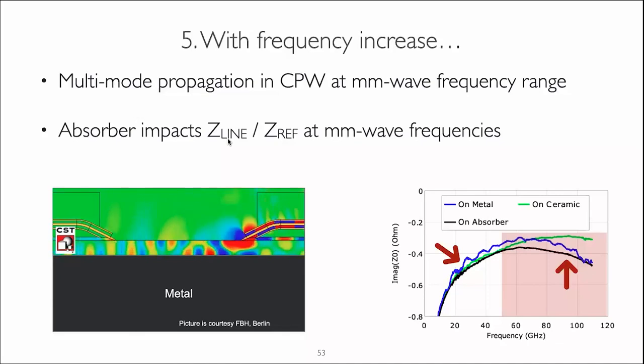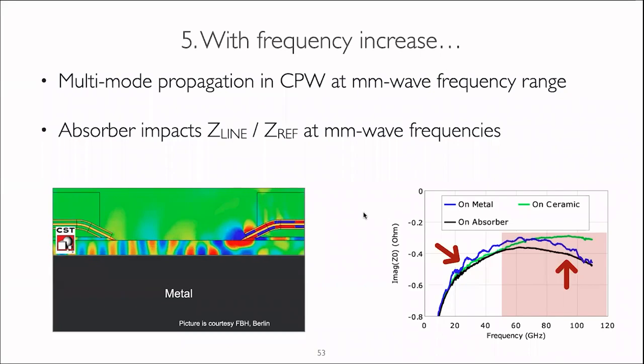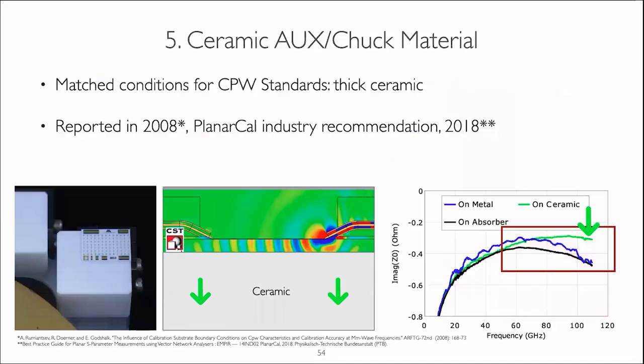Engineers became aware of this problem already at measurements of 20 and 40 gigahertz, and the solution that engineers used previously was to isolate the calibration substrate from the impact of the metal chuck by adding an absorber layer in between. This solution works pretty well up to roughly 50 gigahertz, but with the frequency increase, the absorber changes the characteristic impedance of the transmission line and increases the imaginary part of the impedance. Basically, at millimeter-wave frequencies we end up with a calibration reference impedance of a complex nature. And this is not what we actually want.